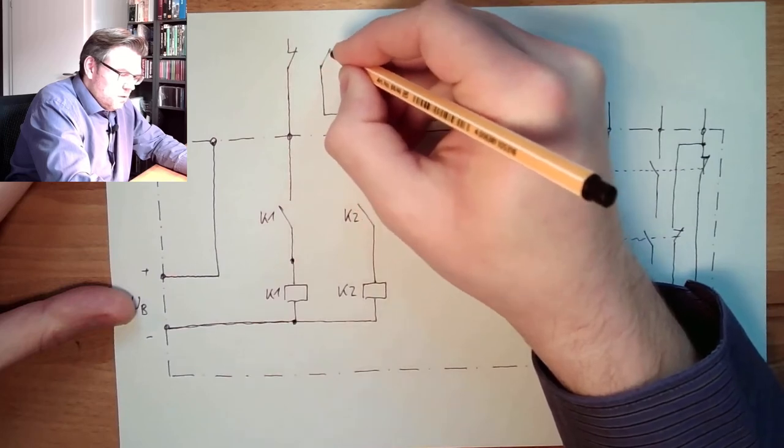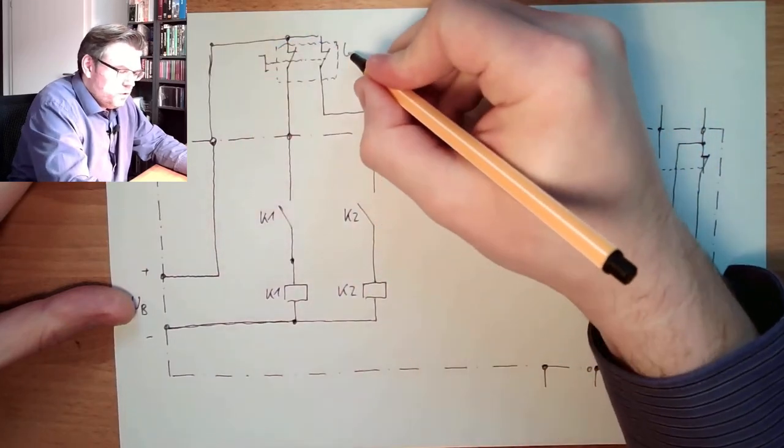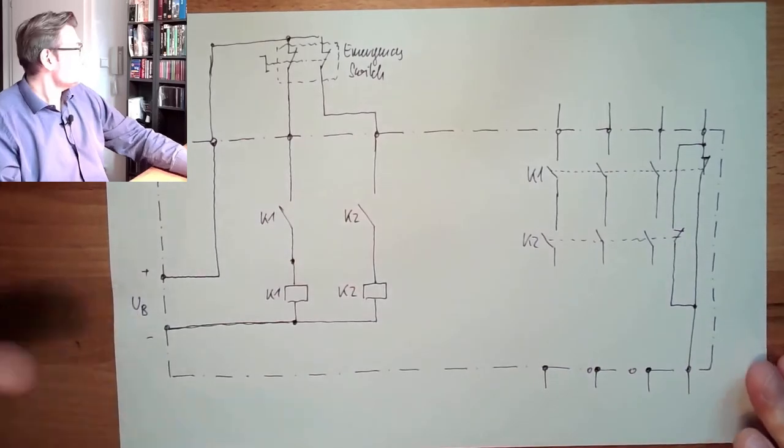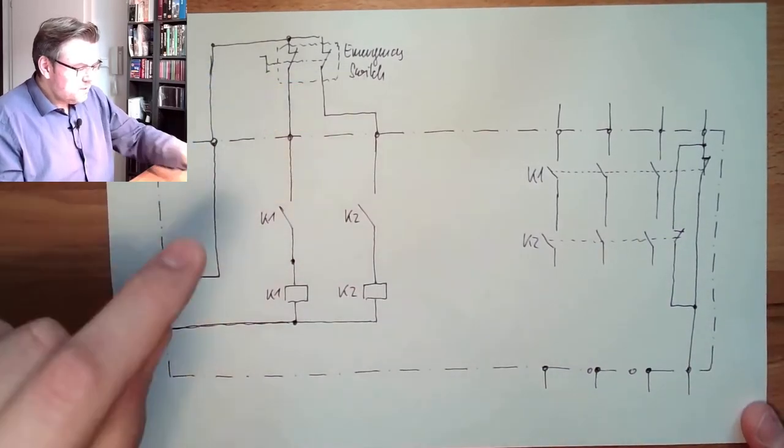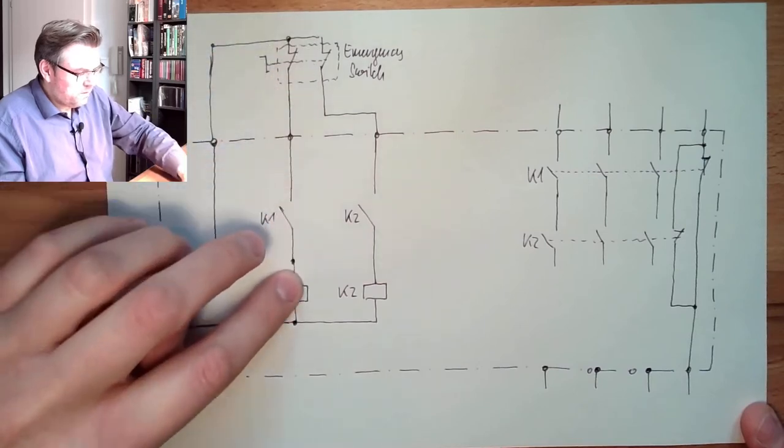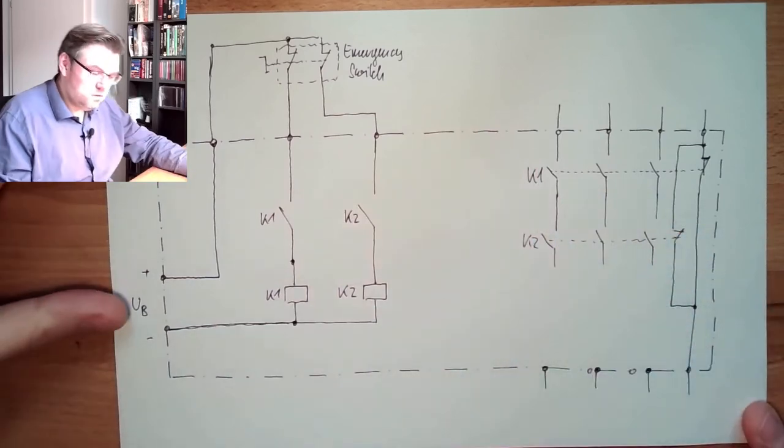And here are two terminals and I just go to a switch, emergency stop switch, which I connect to the plus. Okay, so this here is the emergency switch. If I push this, I will open here. Plus is no longer connected to here. K1 will open, K2 will open. That's it. Both are open.